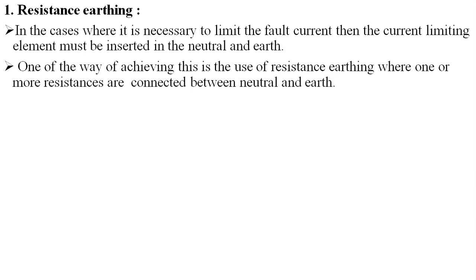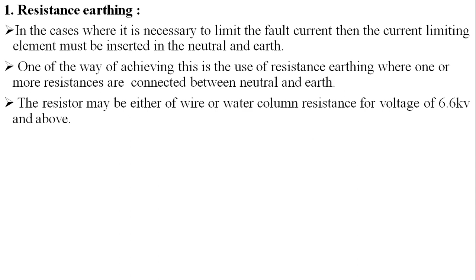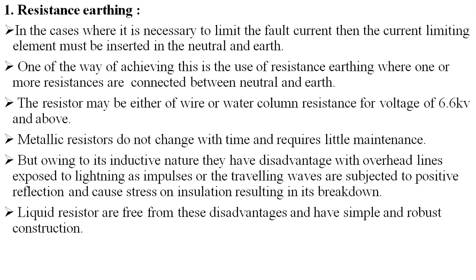One way of achieving this is the use of resistance earthing, where one or more resistors are connected between the neutral and earth. The resistor may be either of wire or a water column resistance for voltages of 6.6 kV and above. Metallic resistors do not change with time and require little maintenance. But owing to their inductive nature, they have a disadvantage with overhead lines. When exposed to lightning, impulses or traveling waves are subjected to positive reflection and cause stress on insulation, resulting in its breakdown. Liquid resistors are free from these disadvantages and have a simple and robust construction.